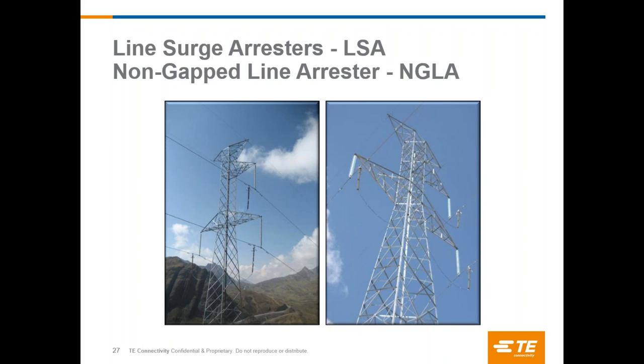Line surge arresters can also be used for control of switching overvoltage profile along the line, as a substitute for pre-insertion resistors, and they work very well together with controlled switching. They are also used for extended substation protection, reducing both amplitude and steepness severity of the incoming voltage entering at air or at GIS substations. In this case, flashover risks near the substation are eliminated.